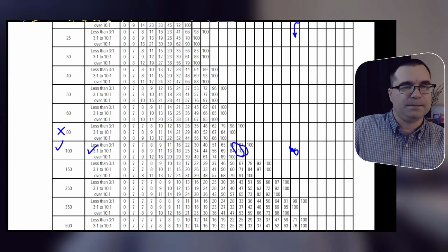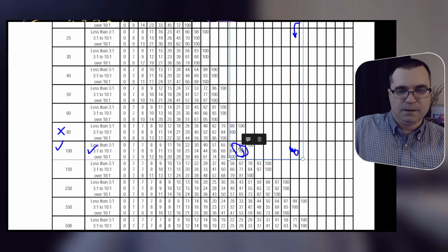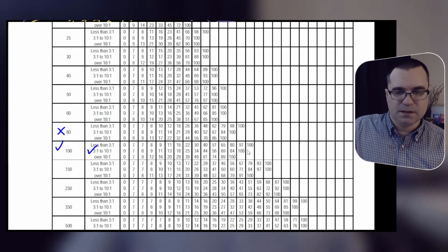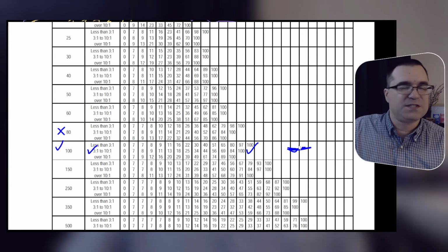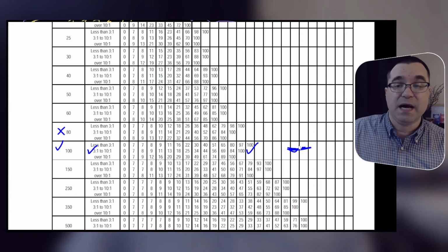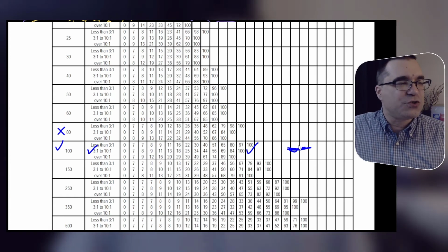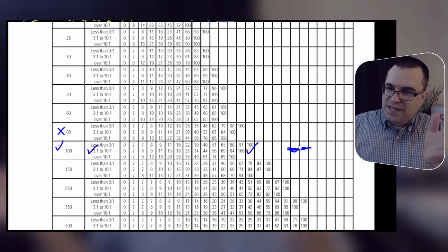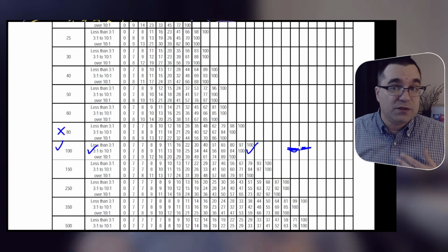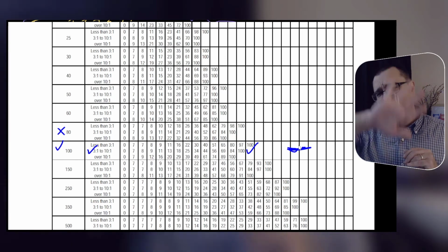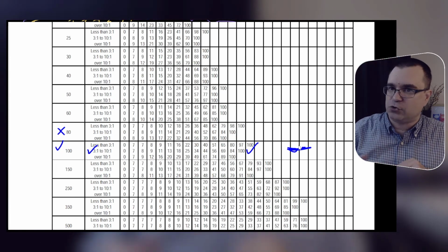Okay, let me clean that up maybe a bit better. Closest number that we get here is 100, right next door. So that means that here, it's still 100. That means 100% of that face is allowed to be unprotected. What does that actually mean? It means that the nearest perceived danger, which is the middle of the street for this face, the west face, is far enough away that the whole west face is allowed to be unprotected.